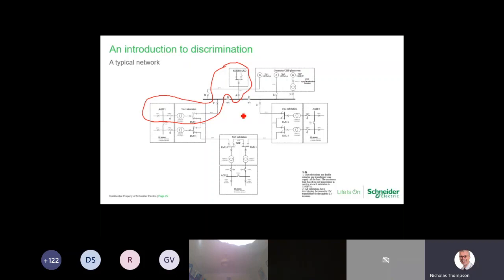In the overall grand scheme of things, a consultant would also have to consider this aspect as well, alongside all the other substations, to determine what the overall fault level is going to be, not only for the main switchboard and the bus bar inside the main switchboard, but also the ring as well, what the fault level is likely to be on that one.